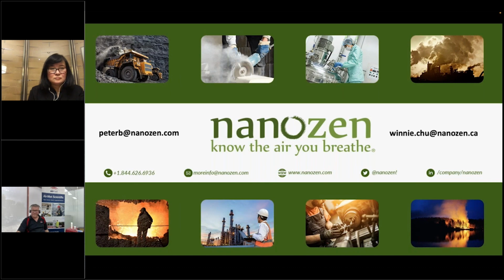Thanks. Is the method for the use of the machine, the Nanozen, the DustCount, accredited for use in legislated workplaces, so mines, quarries, etc.? It's definitely not yet. We are trying to change the status quo by working with the industry association first. OSHA says yes, but it's not the regulatory approved method. It is still an alternative method for now, and we are trying to push the regulation changes. I think the state of Western Australia allows you to put your data onto the regulatory website as a backup or a reinforcement of the legal test.